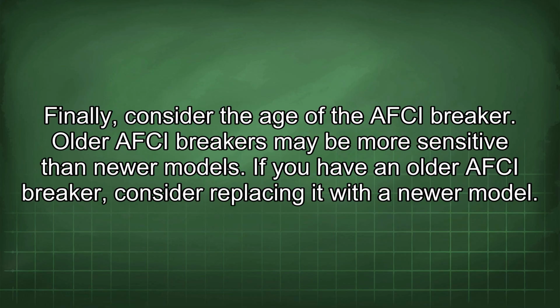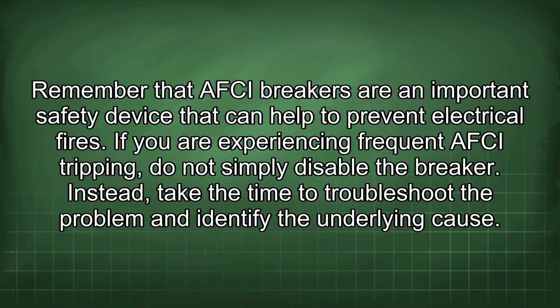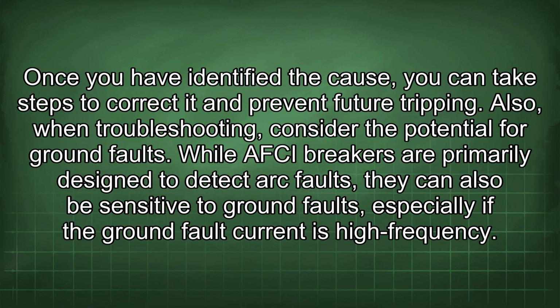Finally, consider the age of the AFCI breaker. Older AFCI breakers may be more sensitive than newer models. If you have an older AFCI breaker, consider replacing it with a newer model. Remember that AFCI breakers are an important safety device that can help to prevent electrical fires. If you are experiencing frequent AFCI tripping, do not simply disable the breaker. Instead, take the time to troubleshoot the problem and identify the underlying cause. Once you have identified the cause, you can take steps to correct it and prevent future tripping.